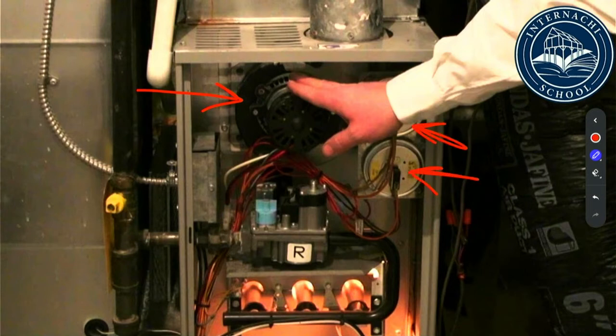You know what those are, Jason? Those are pressure sensor diaphragms of some sort. Yeah, their actual name is a pressure differential switch. So when these things are going, there's usually going to be a tube. And it's kind of hard to see in this picture, but there's going to be a tube that goes to the inducer fan housing motor. And sometimes it's going to be inside the heat exchanger. Sometimes it's going to be in the housing motor. So sometimes it'll be a negative pressure. Sometimes it'll be a positive pressure. But anyway, it's going to change the pressures. That's going to send a signal back to the computer saying, yep, you're good. Continue on.